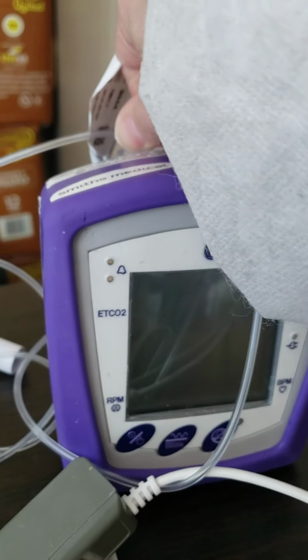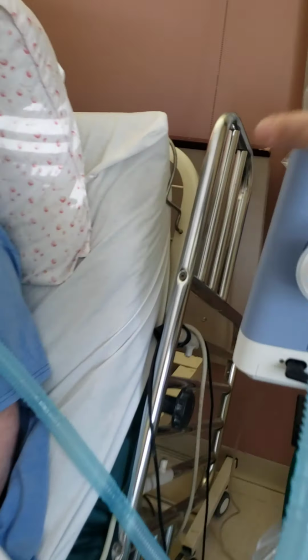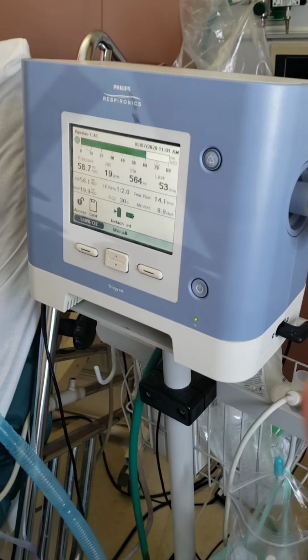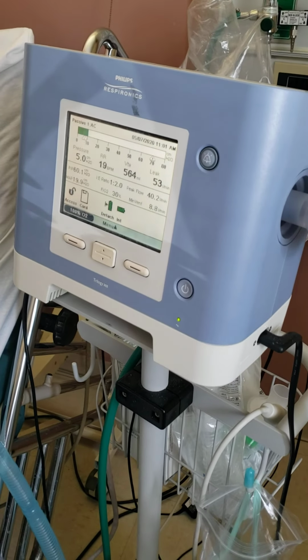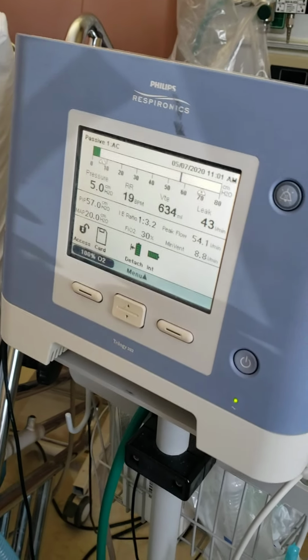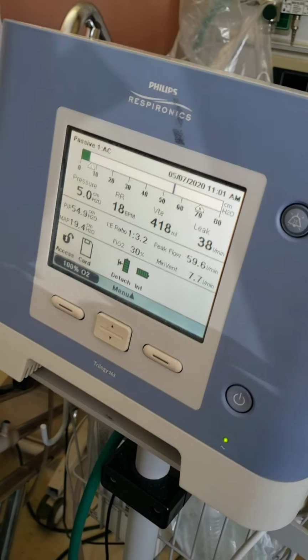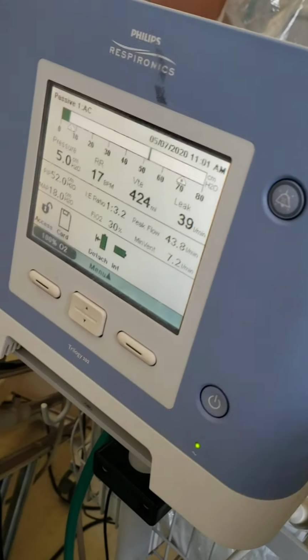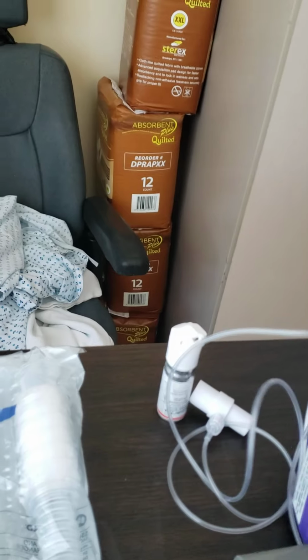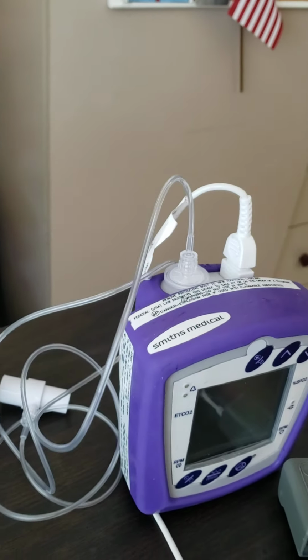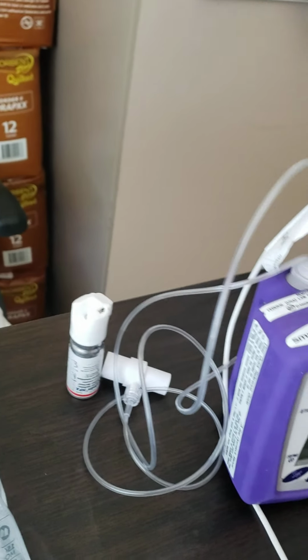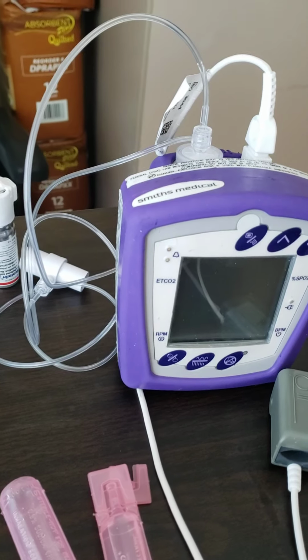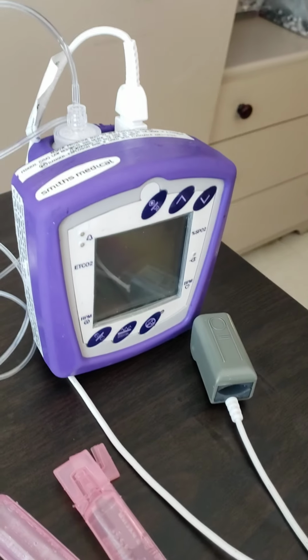End-Tidal CO2 is the measurement of whether or not a person is ventilating. The ventilator isn't just assisting with oxygenation, because if oxygenation was the only issue, we would just put him on a nasal cannula, an oxygen mask, something like that to deliver oxygen. Jack's problem is actually that he cannot ventilate. Ventilating is not breathing, it's the removing of carbon dioxide from your system. This tube attaches to the airway and takes a bit of his exhaled breath, analyzes it inside this machine, and lets me know if he's properly ventilating. If he's not, we'll have to change the settings on the ventilator.